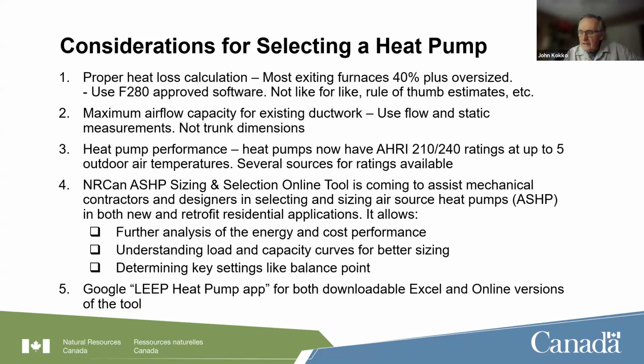Or a rule of thumb like the tons per square foot that some people use. The next thing to do after we get a proper heat loss is make sure we know what the maximum capacity of the existing ductwork is. And the flow and static should be measured, not something like measuring the trunk size to see what it can handle using a duct calculator. This is important because heat pumps are low temperature devices, so you need more CFM for a given capacity because it's being provided at a lower temperature rise.